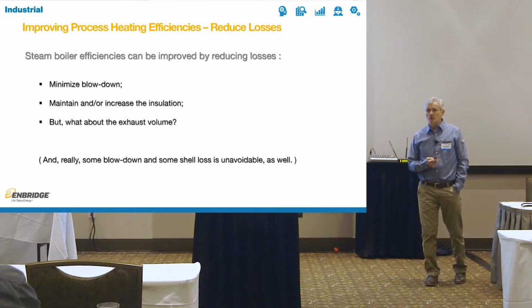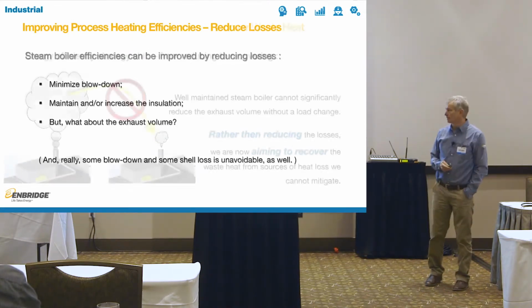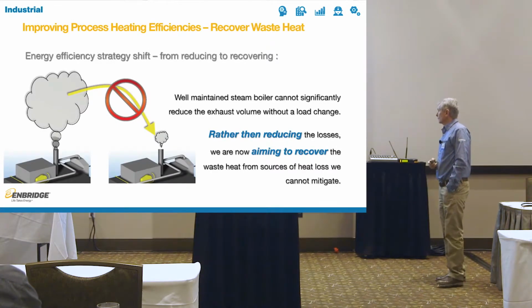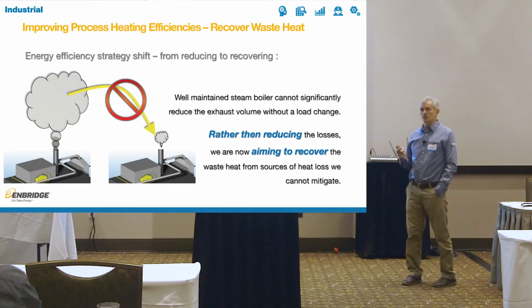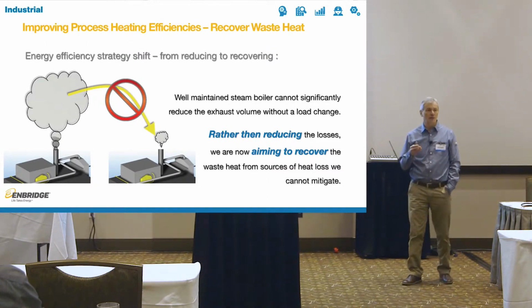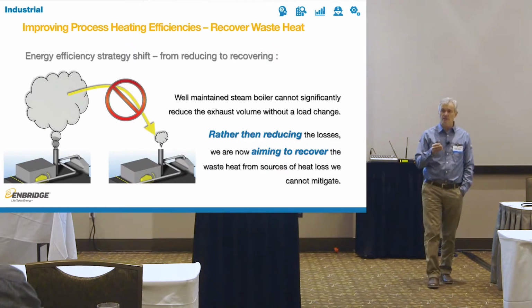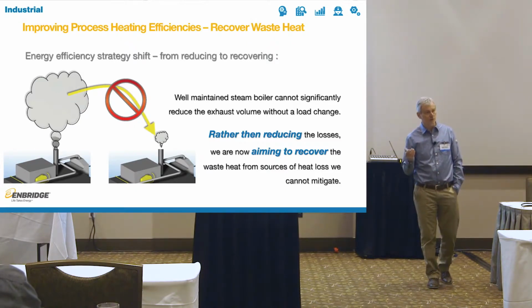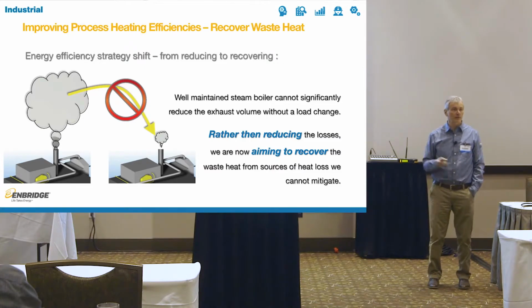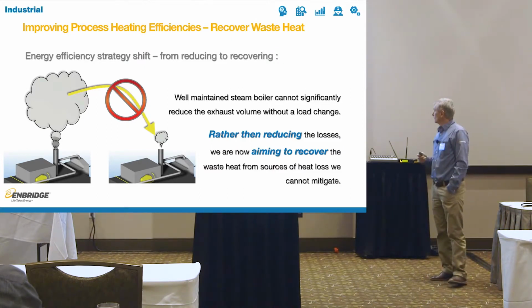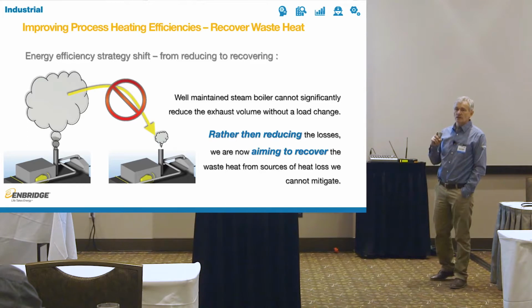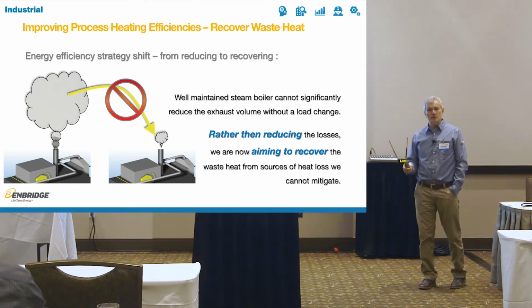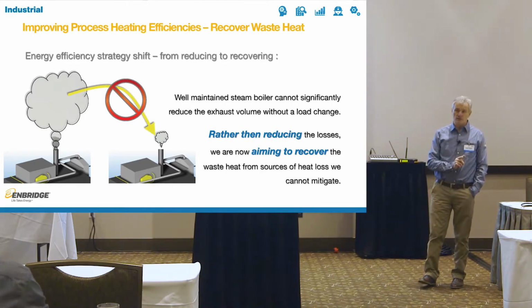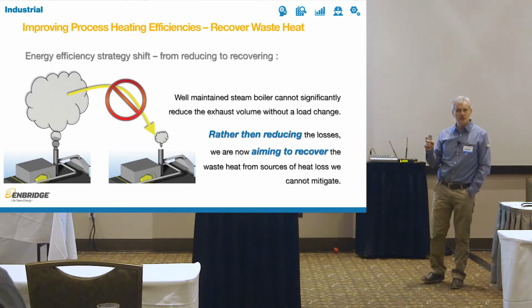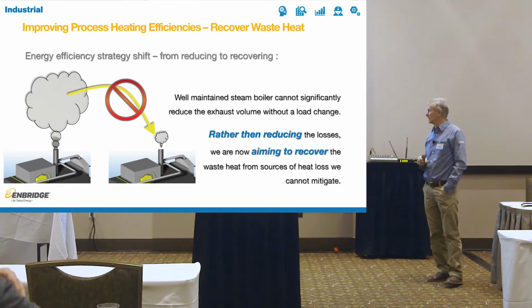What are you going to do with the exhaust volume out of the boiler? 20%, significant. Well, unfortunately, on a boiler, it's not as simple as just turning down the VFD. That's not how it works. Every boiler, if properly maintained, will have a certain amount of volume that needs to be exhausted, and that's it. You're stuck with it. So we are really talking about recovering the heat out of that exhaust rather than reducing the exhaust itself. Now that we know we have to live with the 20% losses in the stack, can we recover that heat somehow?